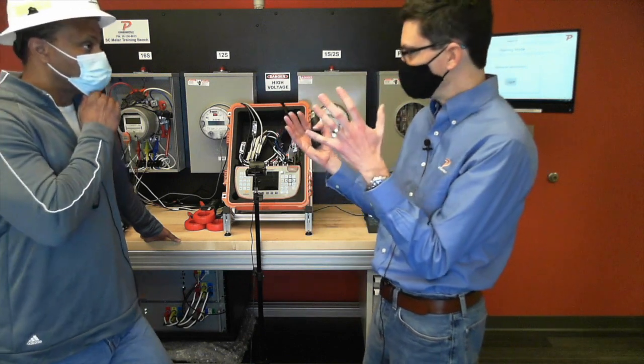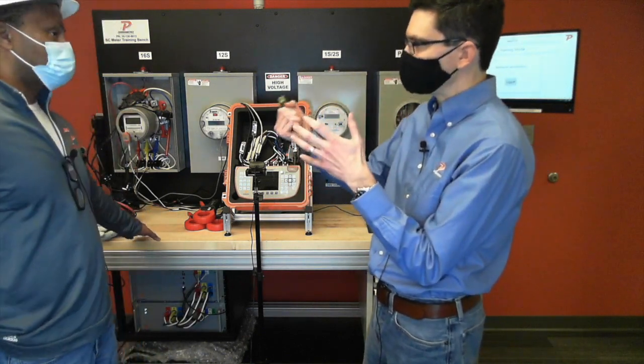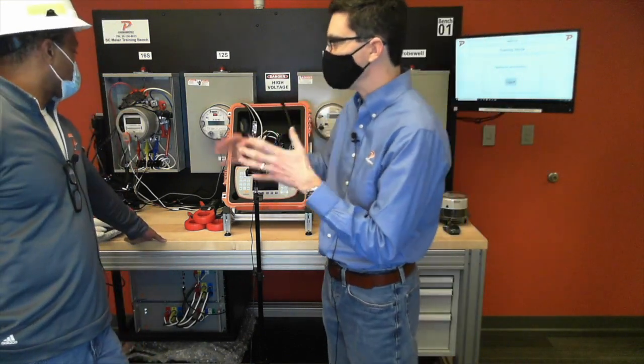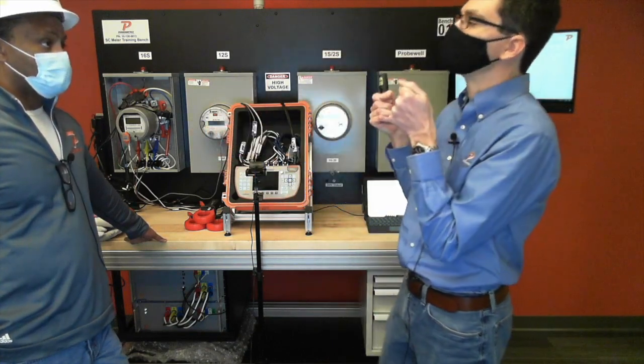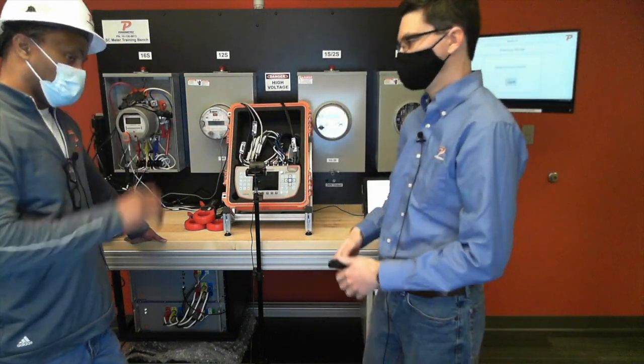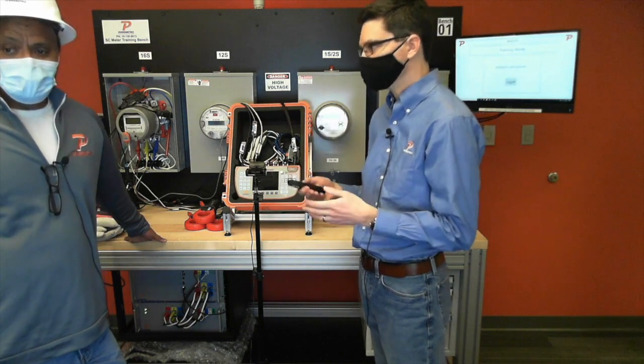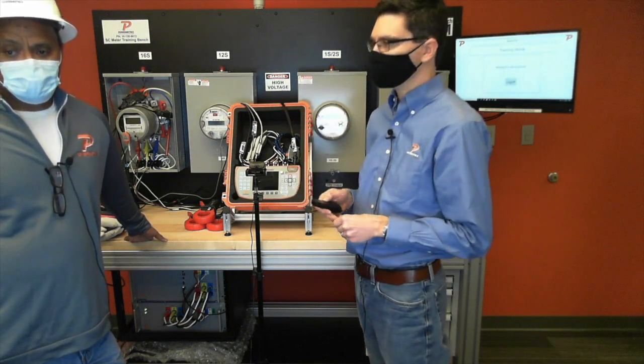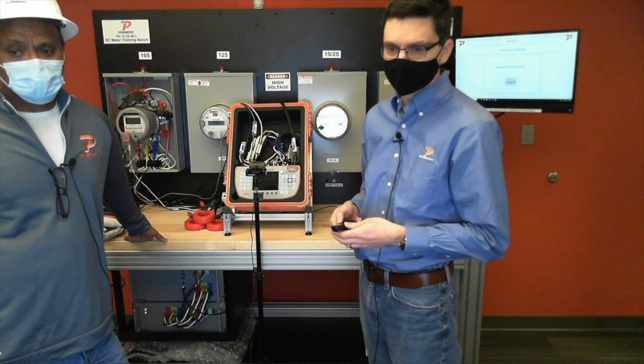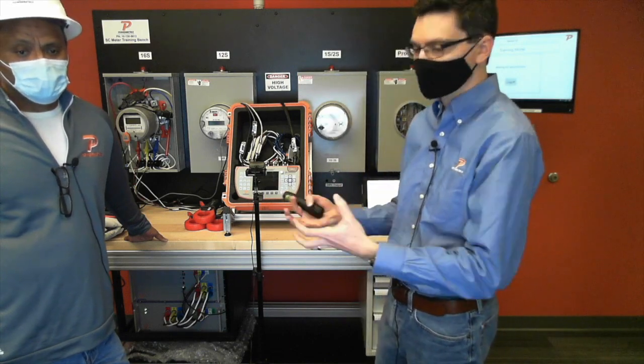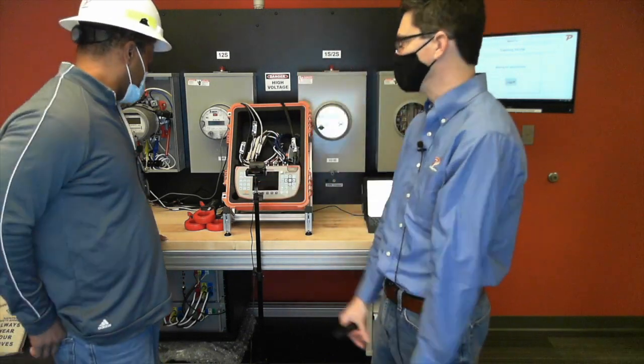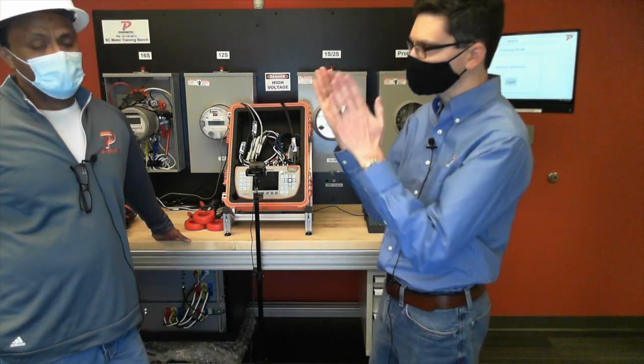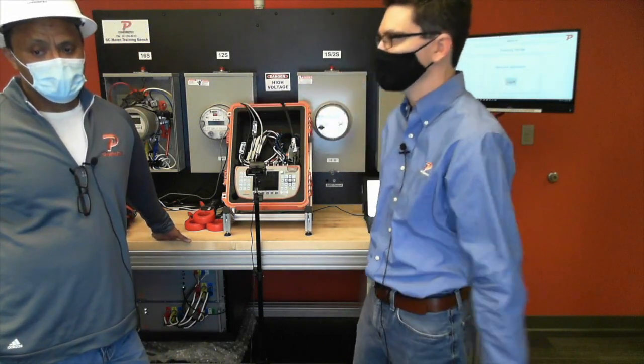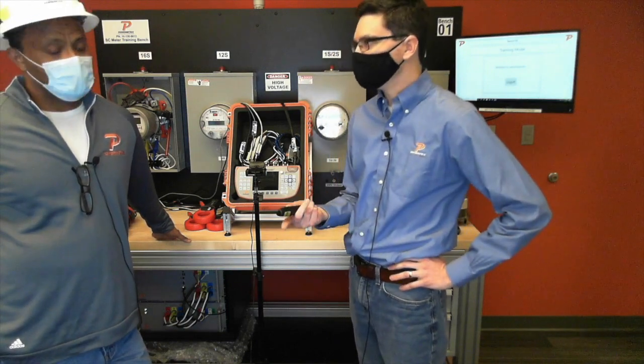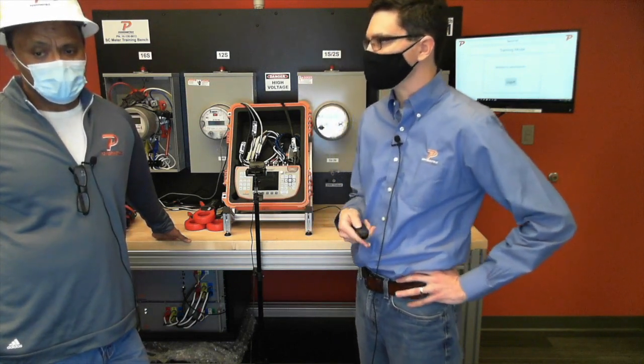So if I don't have a bypass switch to shunt the current as I move it out, what happens if I pull that meter out directly? The current's going to follow you. So arc flash possibility, right? Yes, very dangerous. I'm sure you guys have seen it on your safety videos. An arc flash is real, a big fireball comes up. You don't want that to happen when those jaws don't collapse as you pull out the meter. Make sure you follow those safety guidelines - the higher the current, the higher the voltage, the higher the possibility of an arc flash happening.